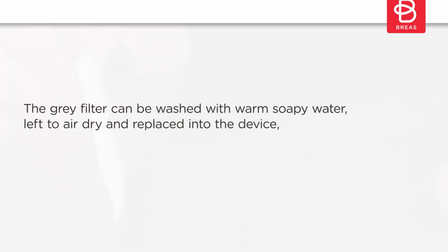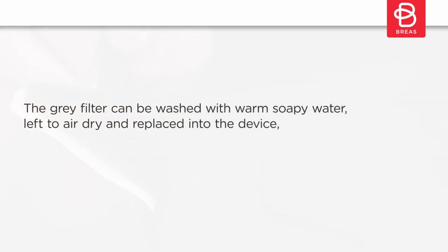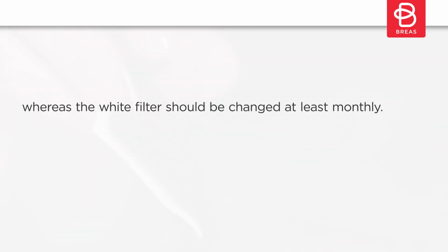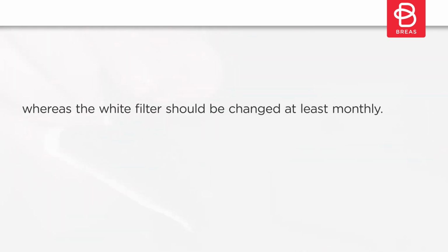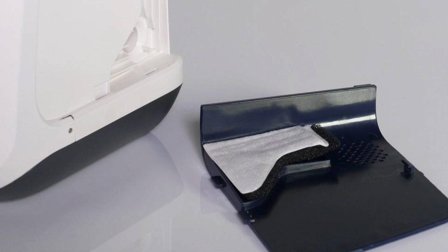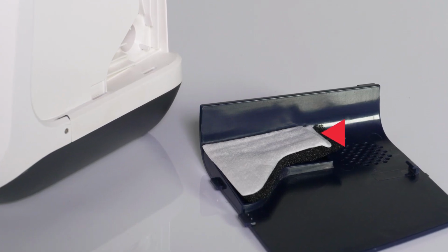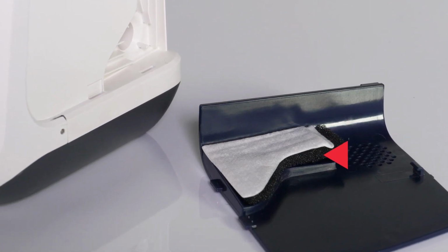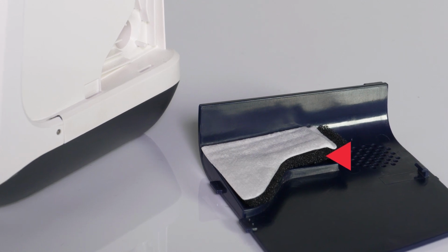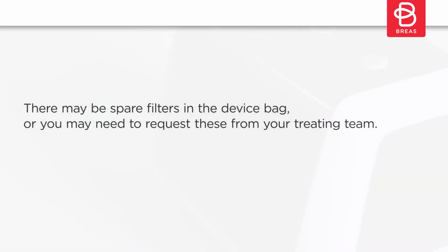The grey filter can be washed with warm soapy water, left to air dry and replaced into the device, whereas the white filter should be changed at least monthly. When replacing the filters, the white filter should be closer to the ventilator and the grey filter should be outermost. There may be spare filters in the device bag, or you may need to request these from your treating team.